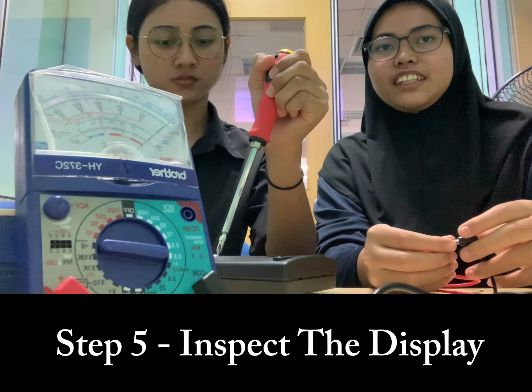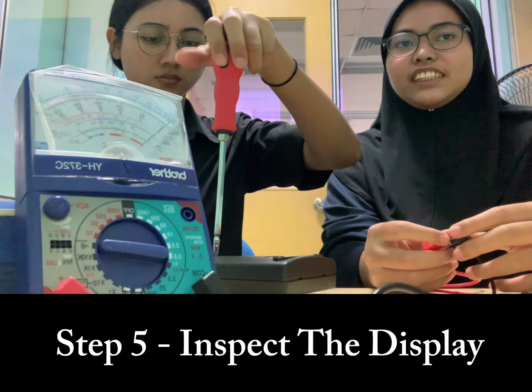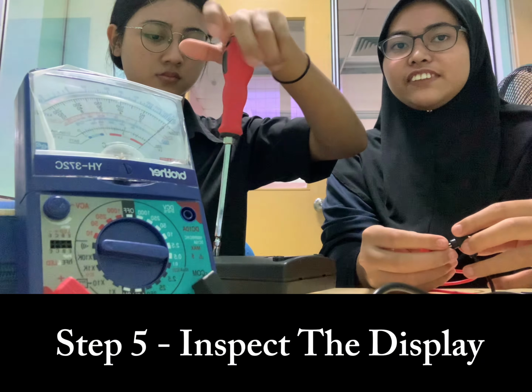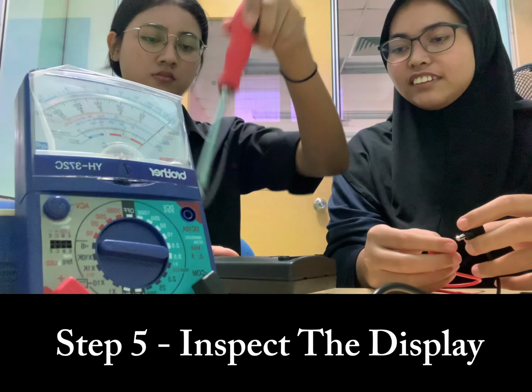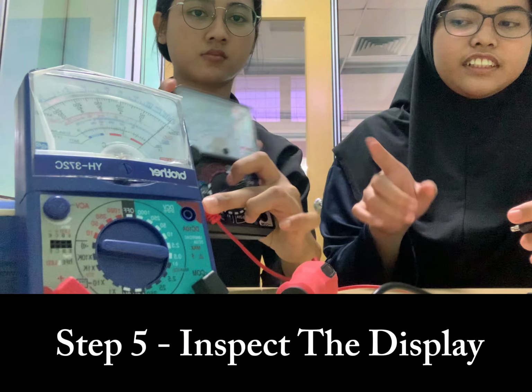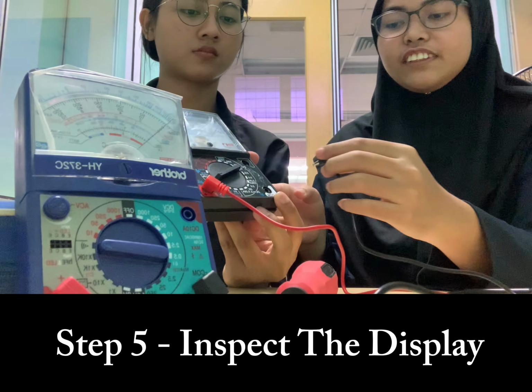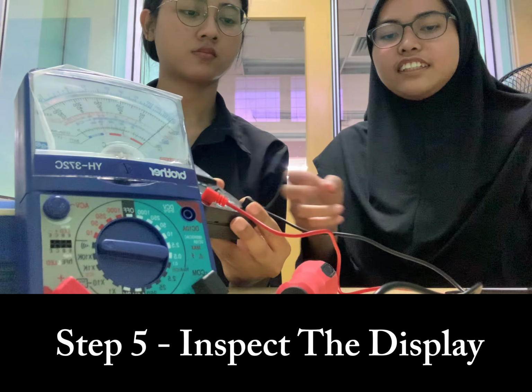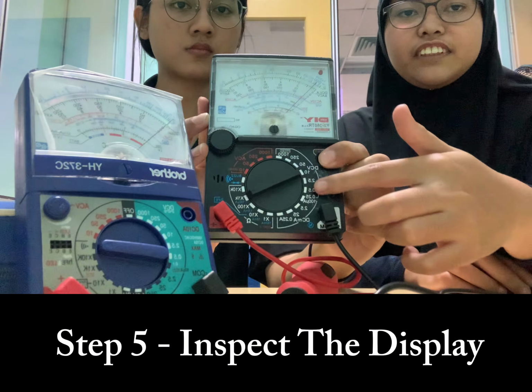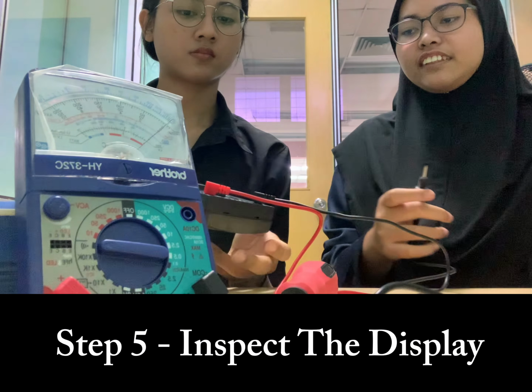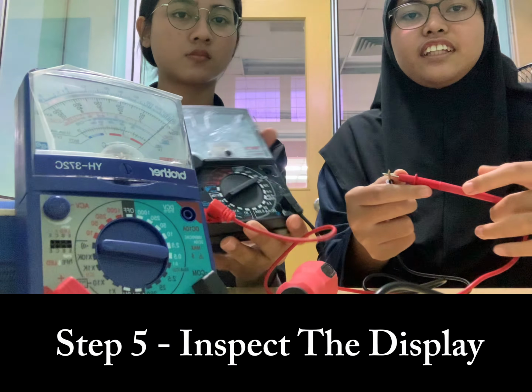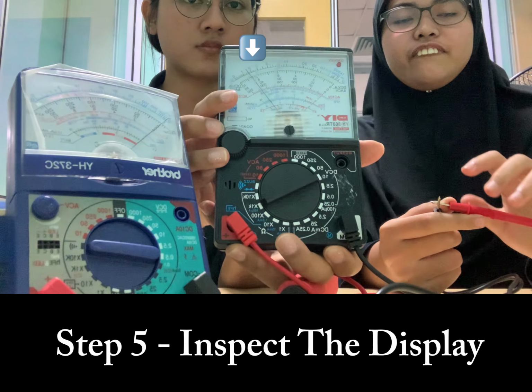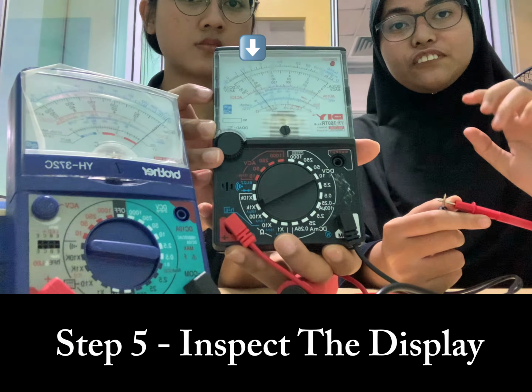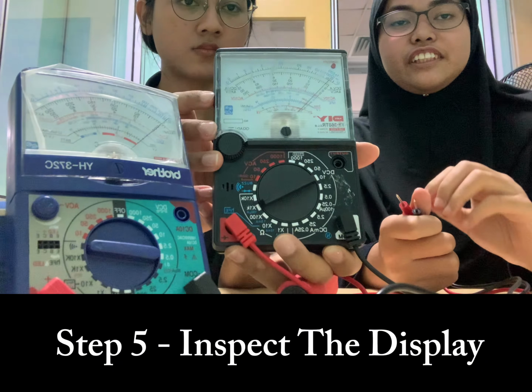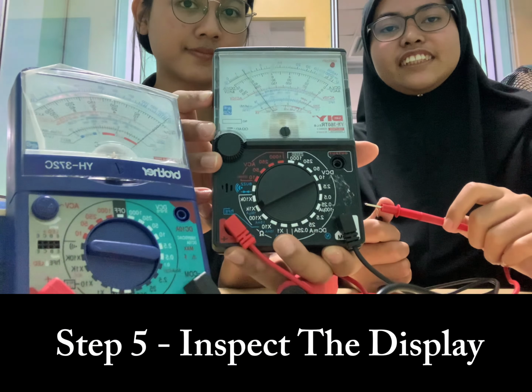Step 5. Close the multimeter to inspect the display. We do this to ensure the display is functioning correctly. If it's blank or unresponsive, it might need repair or replacement. The red probe must be on the red side or live, and the black probe must be on the negative side or common. And the selector switch must be on the ohmmeter side. If the display shows like this, that means the multimeter is good to use. We do this because a faulty display can make it seem like the multimeter isn't working even if it is.